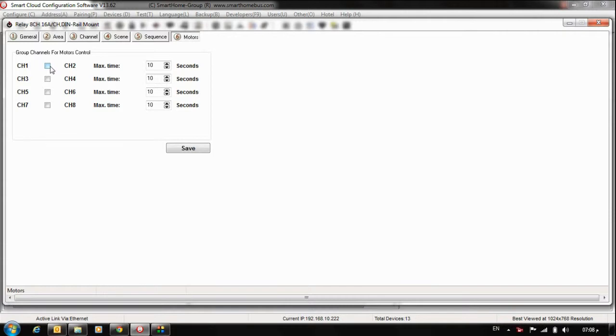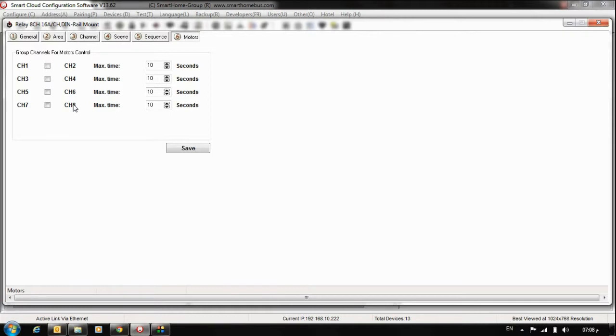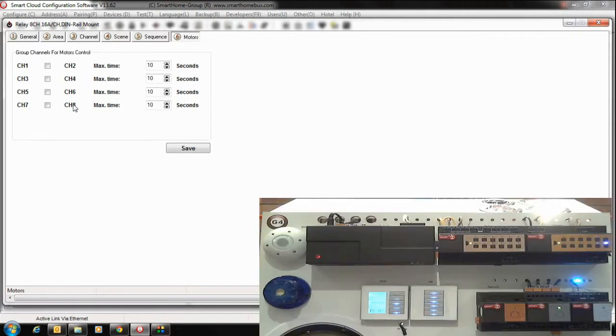About protection, as you notice here we have channel 1 and 2 together, 3 and 4 together, 5 and 6 together, 7 and 8 together. Here, protection, that means you cannot activate two channels at the same time. That means here because you have two phases, you cannot, otherwise you will damage your motors.